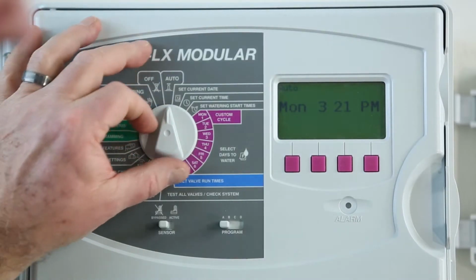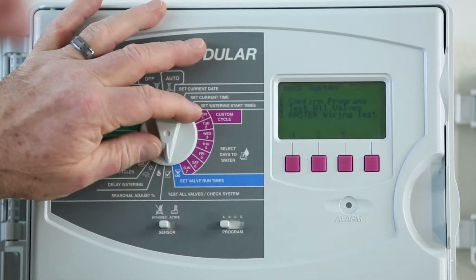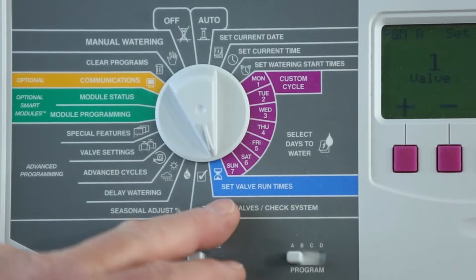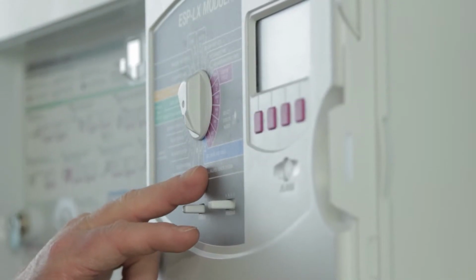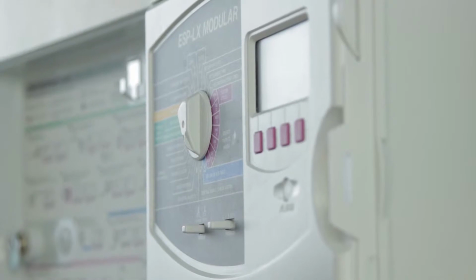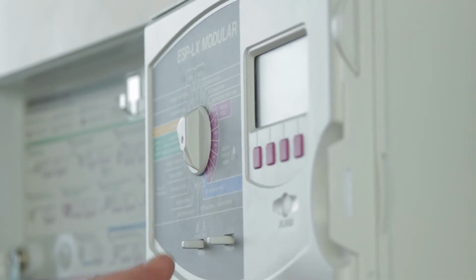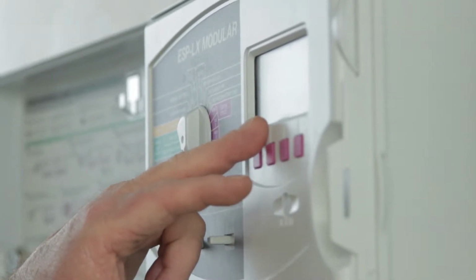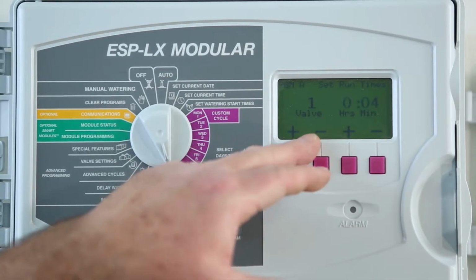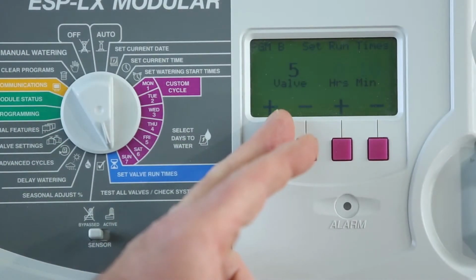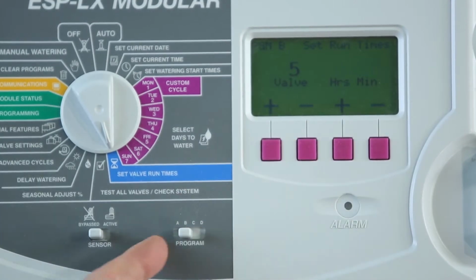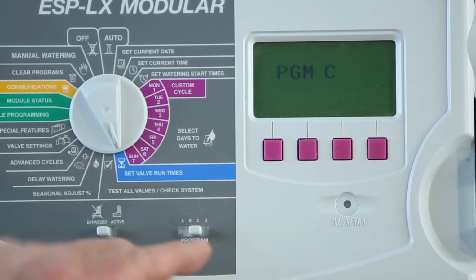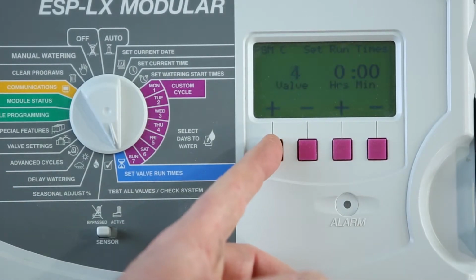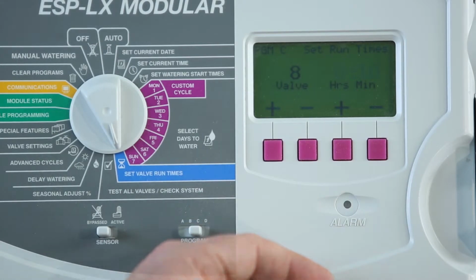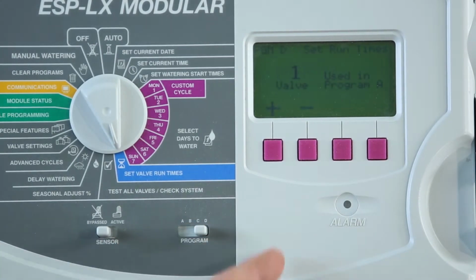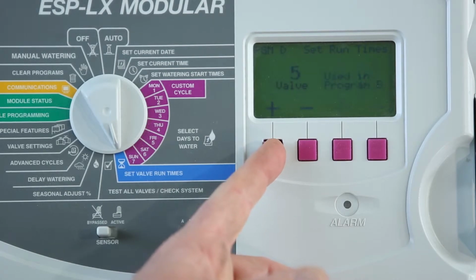To complete the next step, you need to review the irrigation schedule programmed in the host controller. Identify the stations assigned to each program and determine the lowest station number for each program. In our example, Station 1 is the first zone in Program A. Station 5 is the first zone in Program B. Station 8 is the first zone in Program C, and Station 10 is the first zone for Program D.